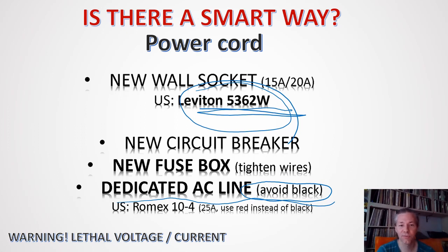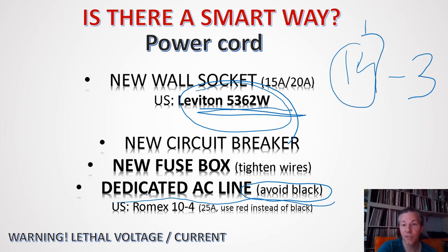How can you avoid that? Only if you install a new dedicated audio line. US electrical wire is labeled with the gauge first, then a dash, then the number of conductors. So the plain ones look like 14-3, meaning gauge 14 with 3 conductors. Look for wires labeled like this. Gauge 14 can carry 15 amps - that's the plain vanilla basic wire in your walls for average outlets in every home in the US.